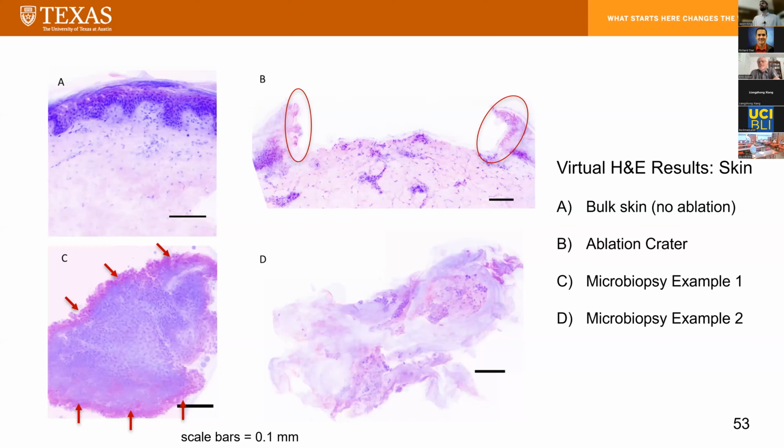But I would think it would be better to change the wavelength and also change the laser type. If you wanted a smaller biopsy, you'd want to go maybe to a fiber laser. I think you could focus it tighter than we can with ours, because we have to go through a 230 micron fiber, and then to focus that and still have enough working distance, it's hard to get it much tighter than what we have.